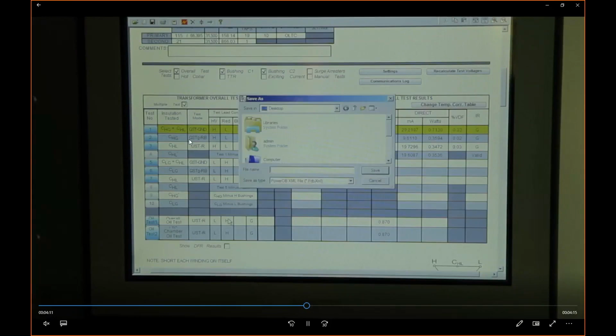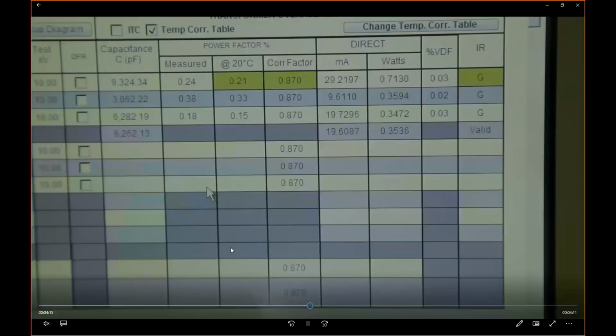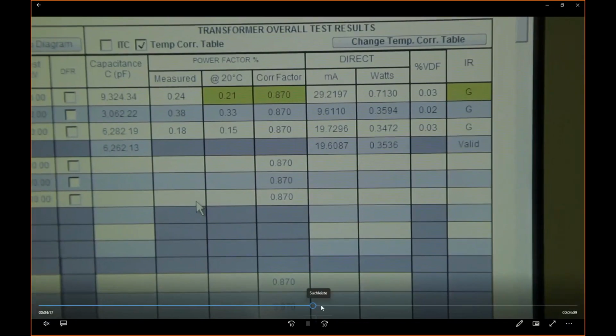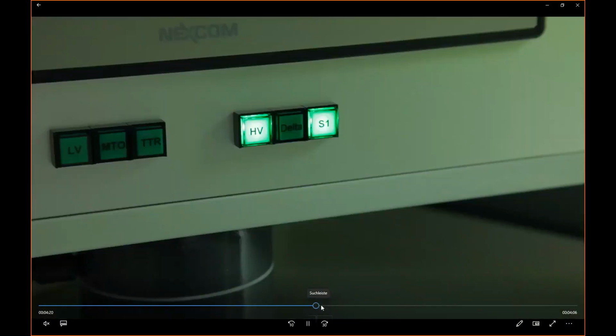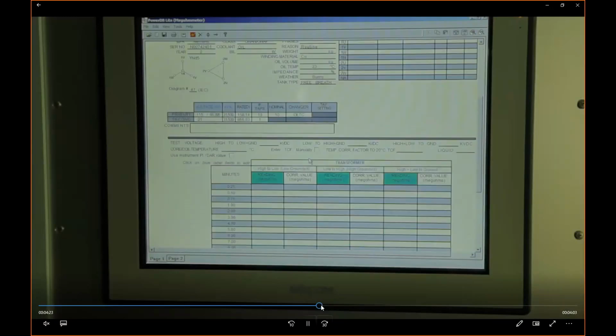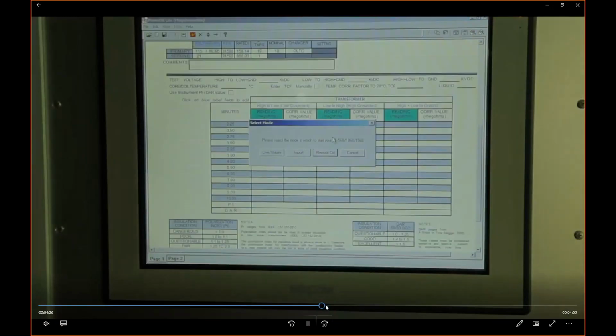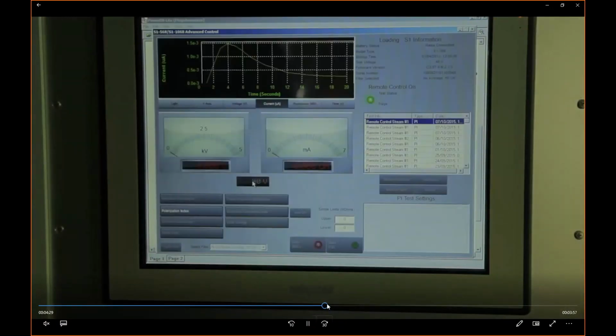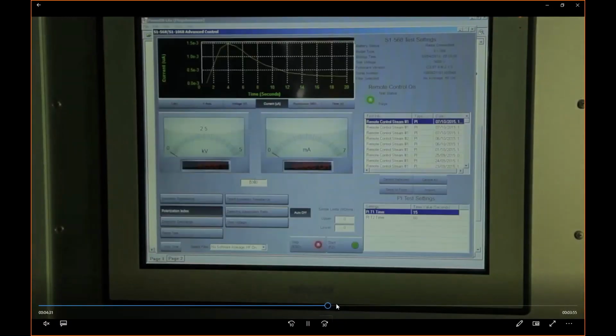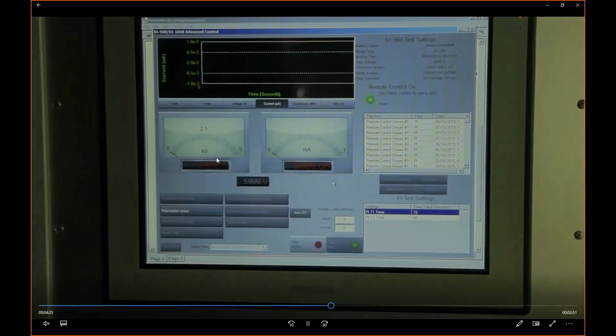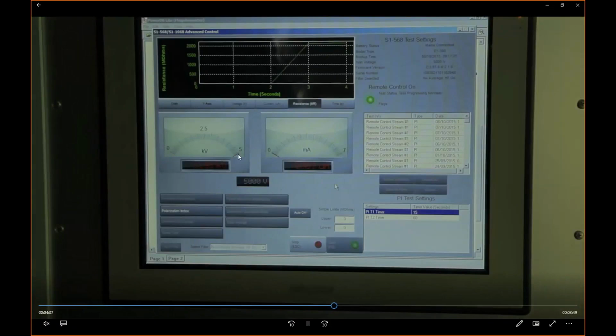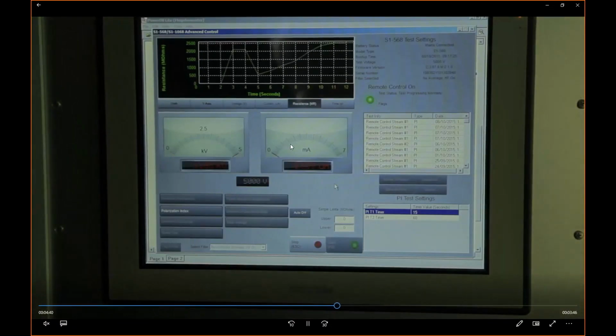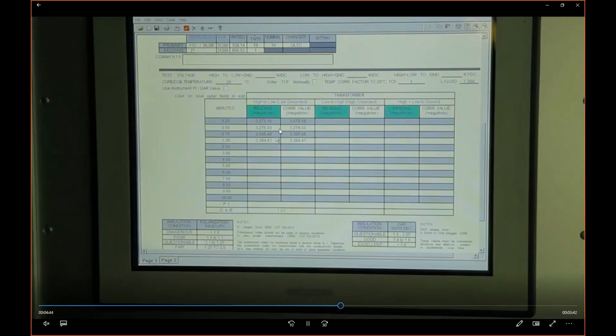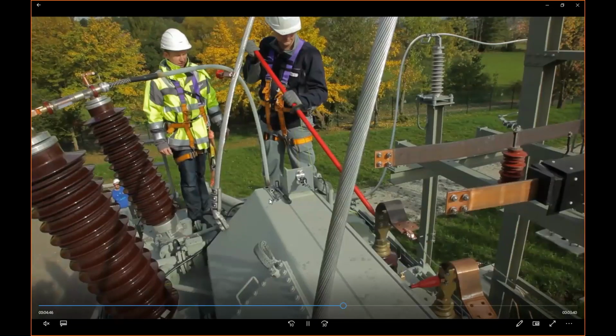So the example is showing you now tan delta testing, where you can do all pieces of insulation, high to tank, low to tank, and so on. And then the next step is you leave the cables as they are, and you simply activate the DC source and collect the data for the insulation resistance. So in this case, you output 2.5 or 5 kilovolt. You see 5 kilovolt in this example. You wait for 60 seconds. You form the table. You calculate PI or DAR.